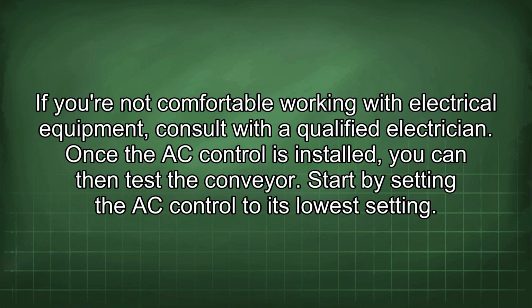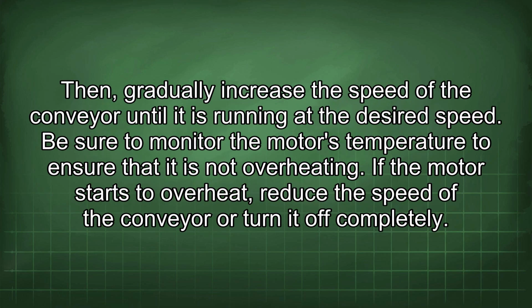Once the AC control is installed, you can then test the conveyor. Start by setting the AC control to its lowest setting. Then, gradually increase the speed of the conveyor until it is running at the desired speed. Be sure to monitor the motor's temperature to ensure that it is not overheating. If the motor starts to overheat, reduce the speed of the conveyor or turn it off completely.